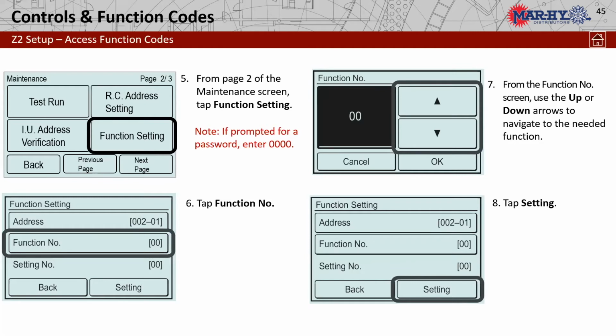So when you highlight function number, you're going to get the numeric value and an up and down arrow. And you will scroll through there to get to your function number and push OK. Now, one thing nice about these functions, these function numbers, they scroll through fast. And you can back up. So if you pass it, you can scroll from 0 to 99 in about 4 seconds. So it does scroll through very fast. But you can back up.